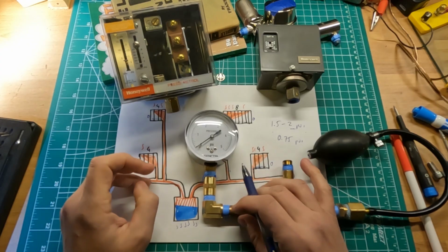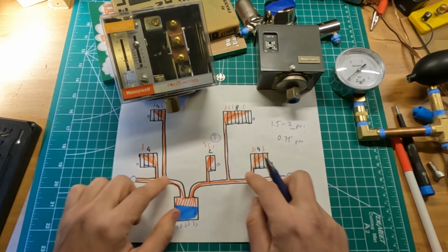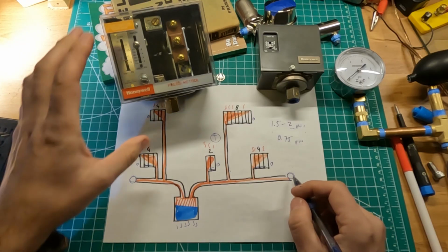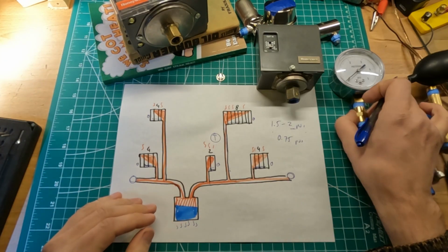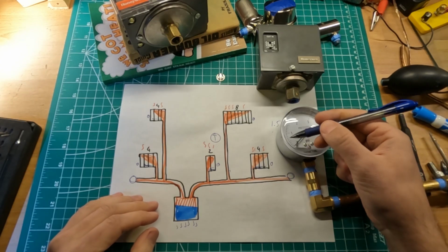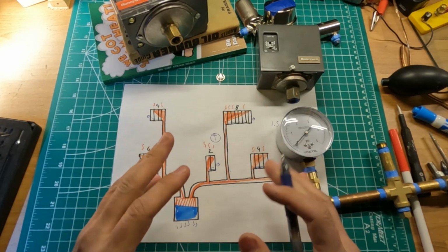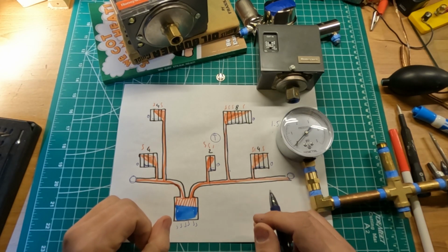If the system is badly working, that means the vents are, let's say, undersized or closed or malfunctioning, they constantly close, then you can see that the buildup is happening way faster, and then you have to figure out what's going on within your system.